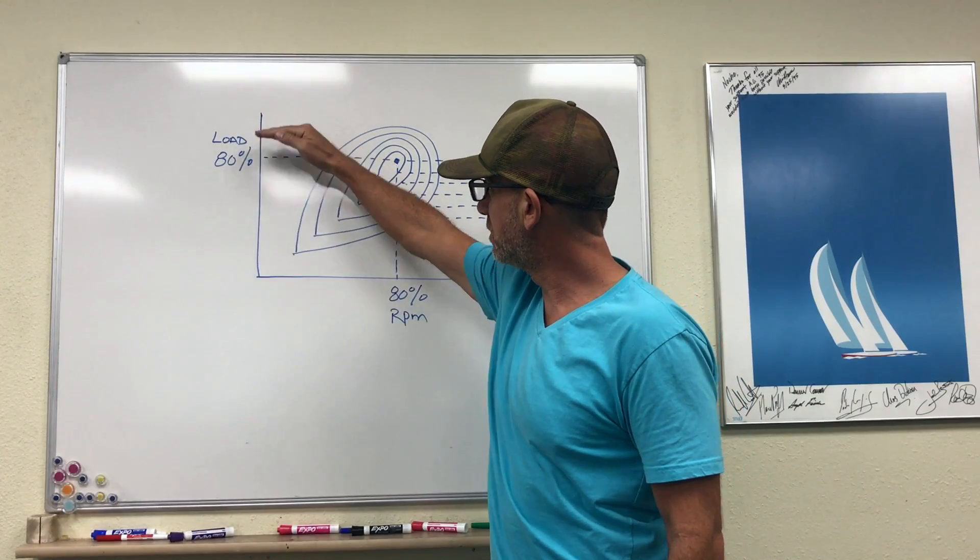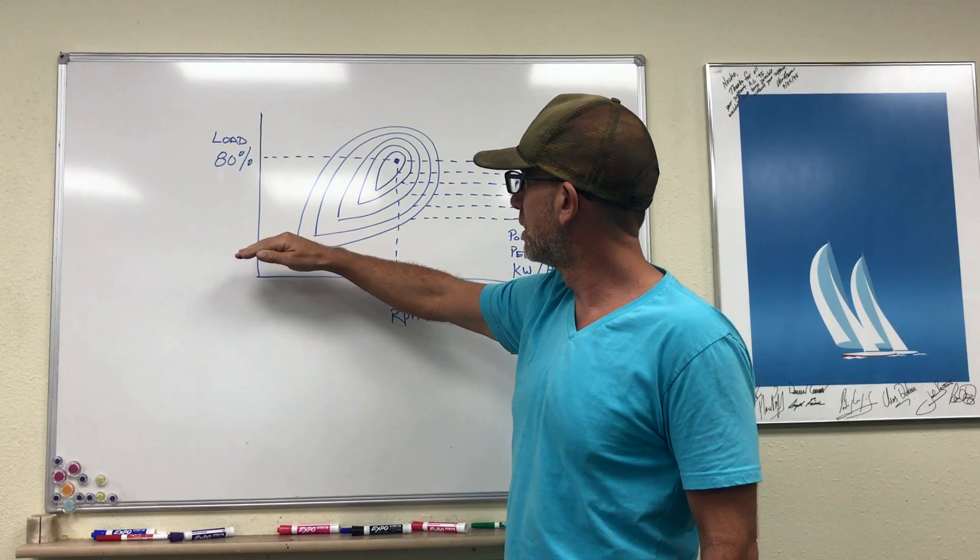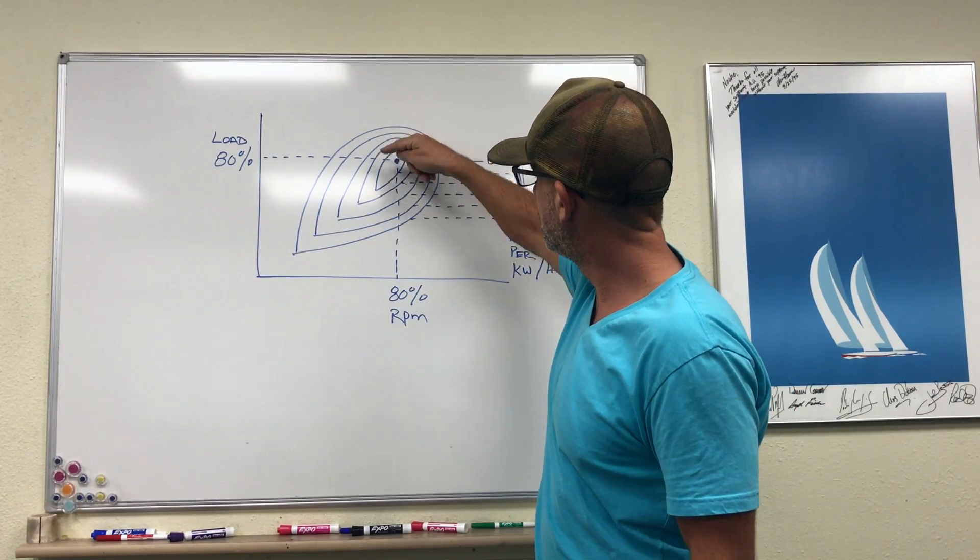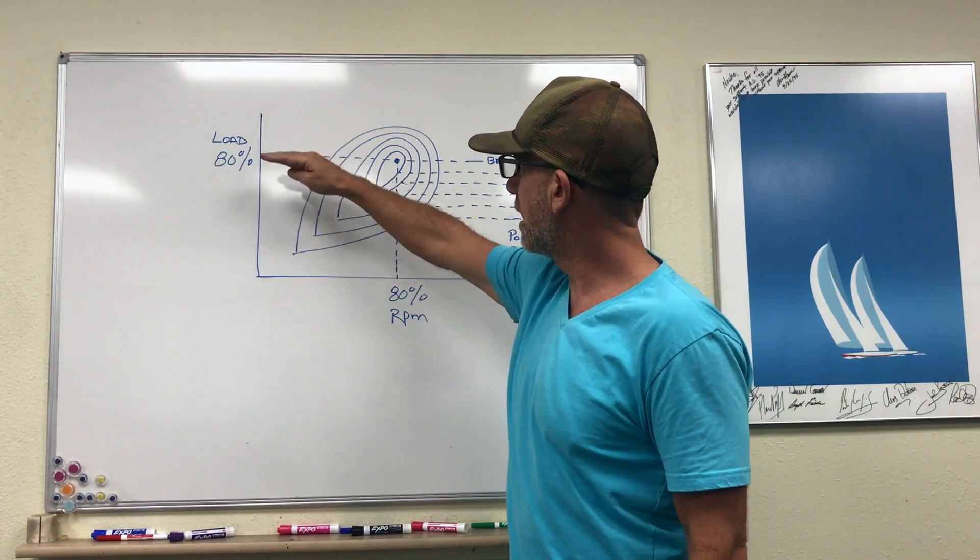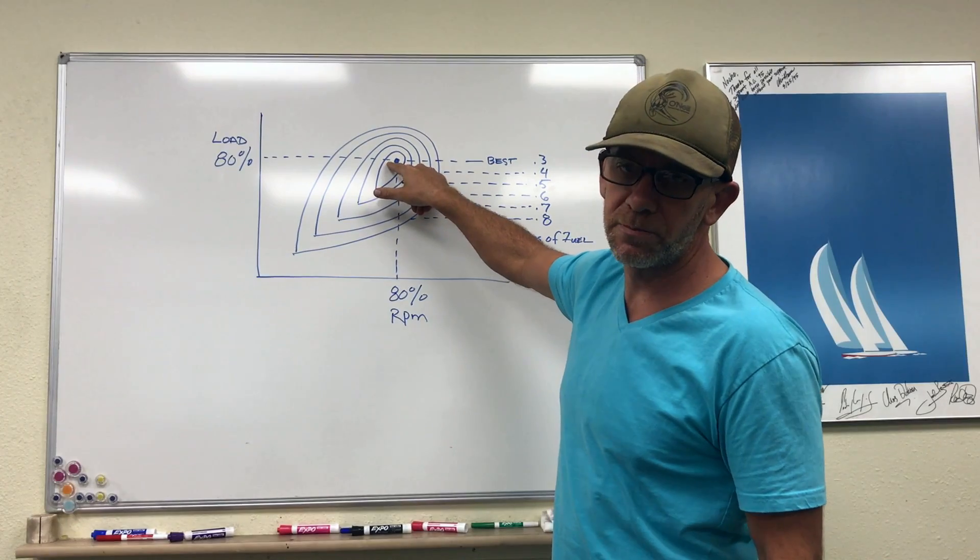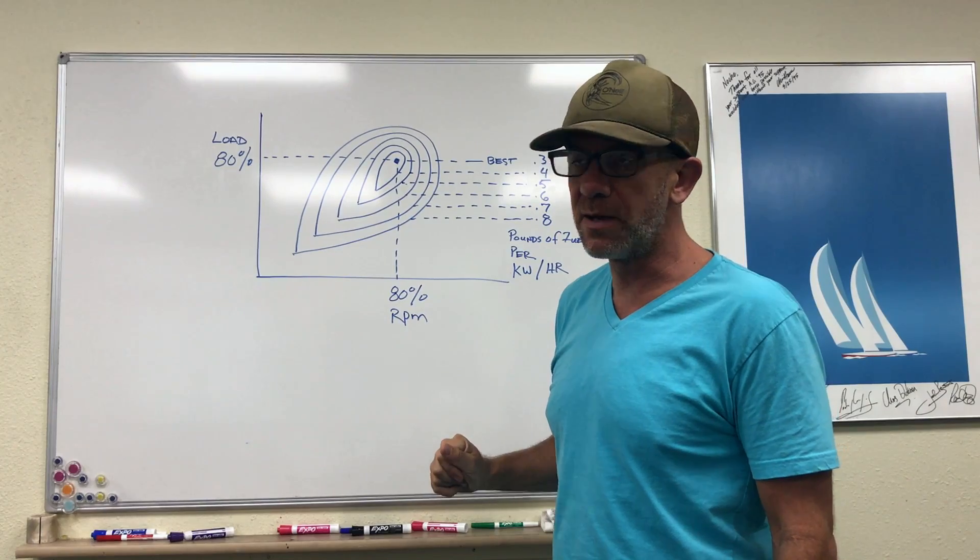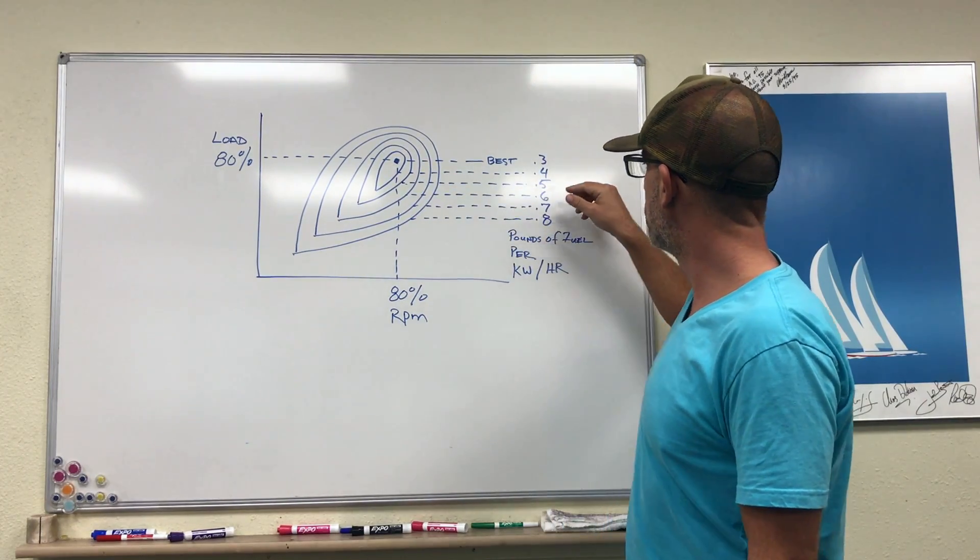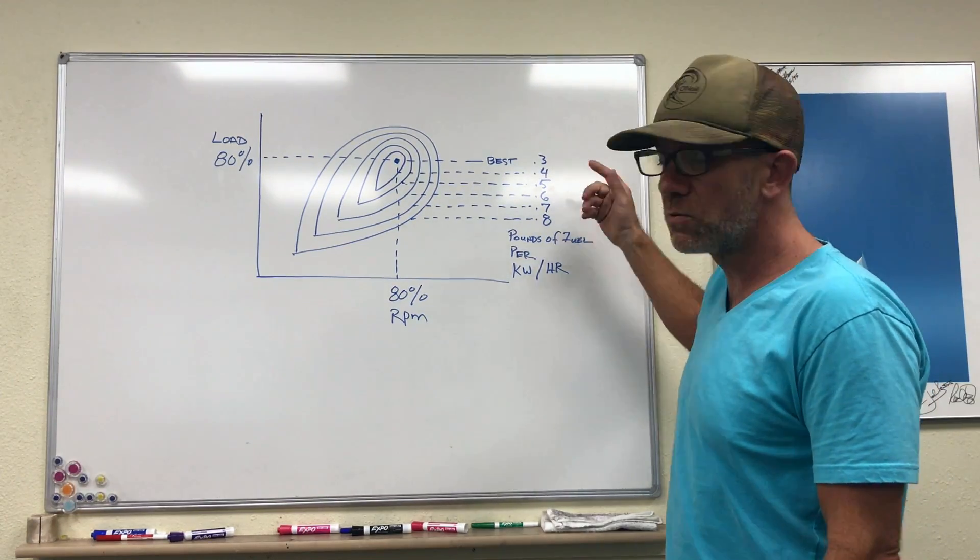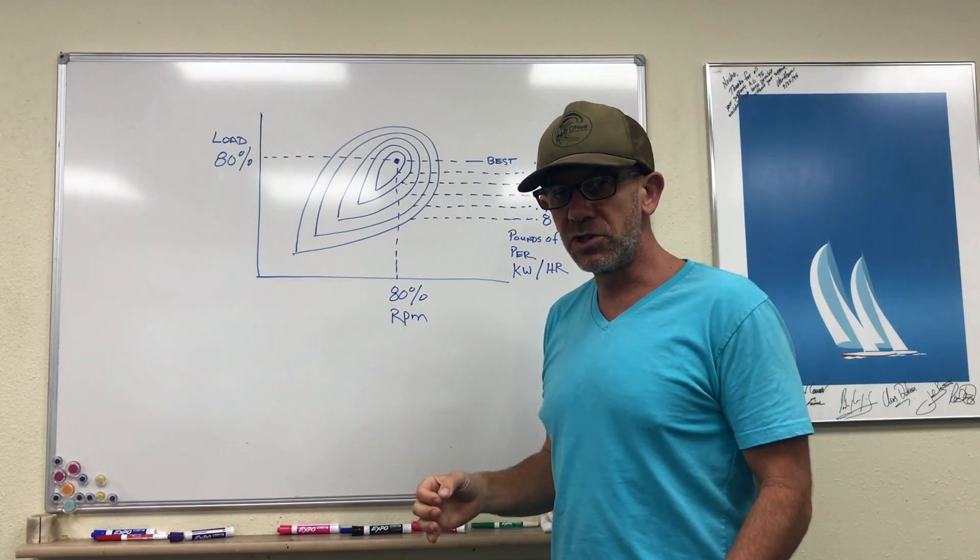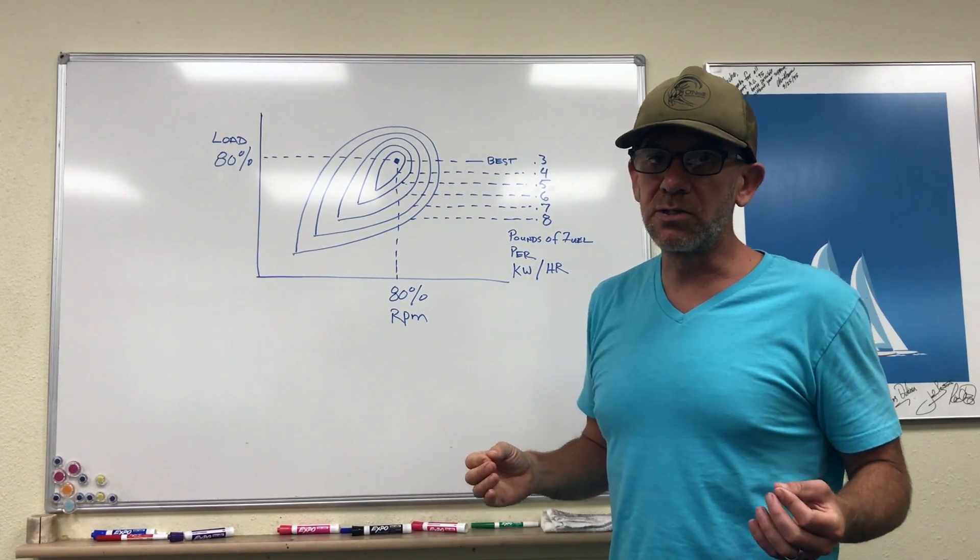If the load changes, so the amount of power that you're drawing from the generator changes, you're going to move into these different concentric circles here. And depending on how far away you move from that theoretical 80% load determines how your efficiency ends up. So as you move away, you go from burning 0.3 pounds to 0.4, 0.5, and so on. And so what that shows is that with a poorly loaded generator, you're not going to get nearly as good of efficiency.